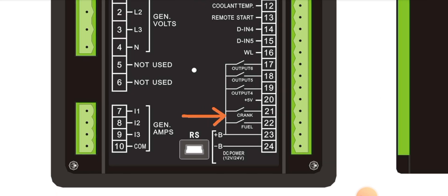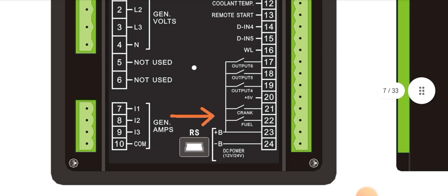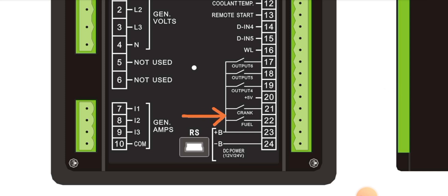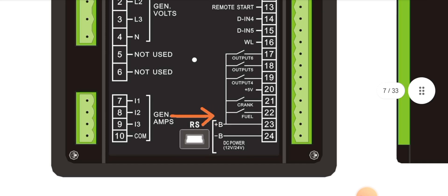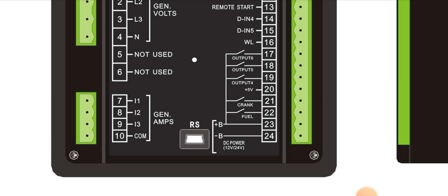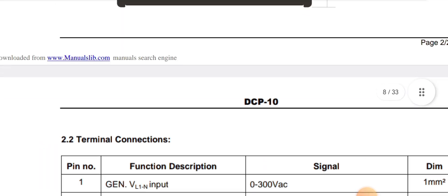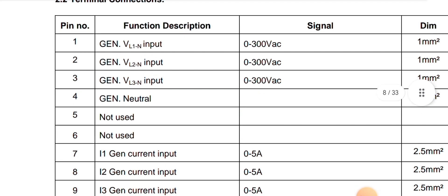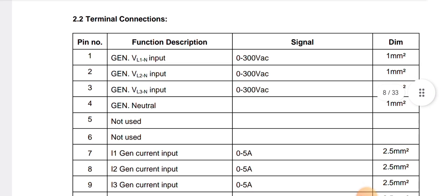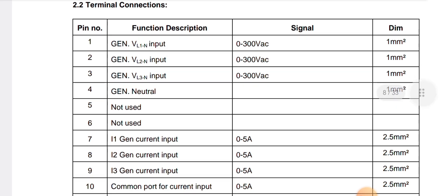Pin 16 is the charging alternator connection. Pins 17 and 18 are output 6 and output 5. Pins 19 and 20 are the 5-volt output. Pin 21 is for the crank relay, pin 22 is the fuel relay, and pins 23 and 24 are the power supply for this controller.